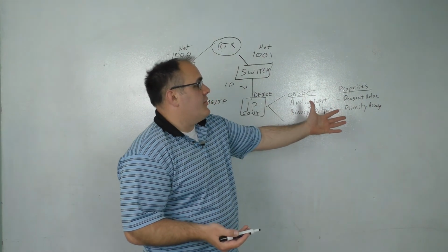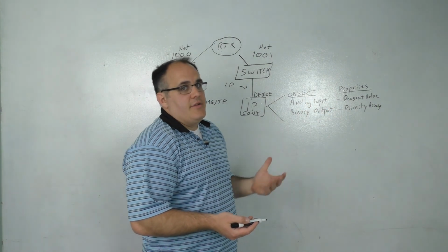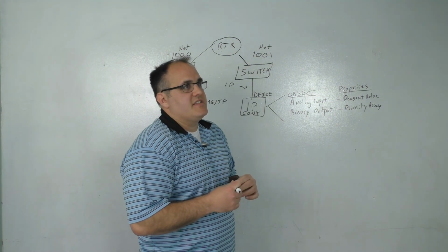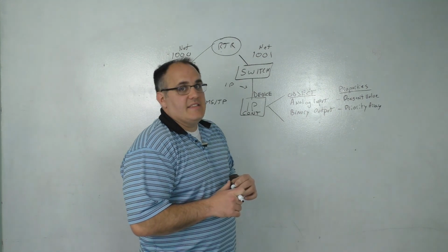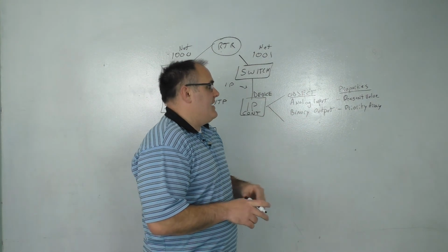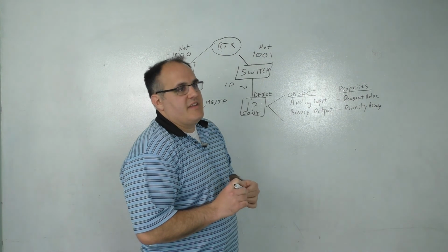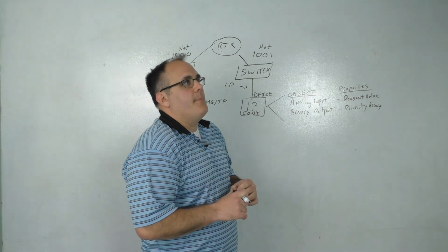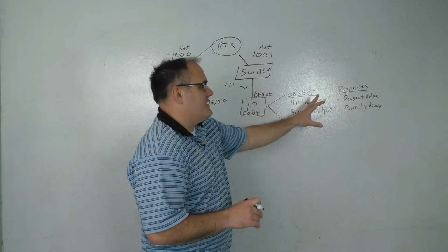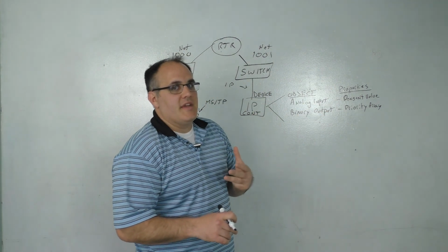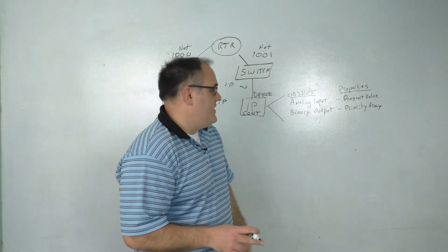And each object is going to have a set of properties. And there's 3 default properties, if I remember correctly. It's device type, device name, and device ID. Those are the 3 default properties for every object. Or object ID, object type, object name. Yes. Those are the three, not device. I was thinking of device. Those are the three properties for every object: object name, object type, object ID. All right, so you have objects, you have properties.